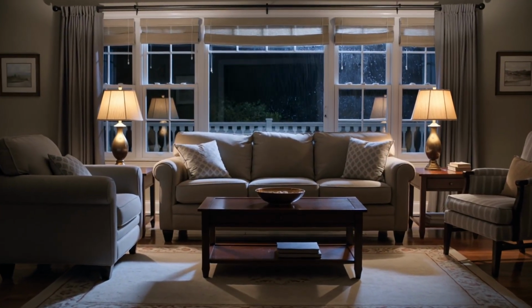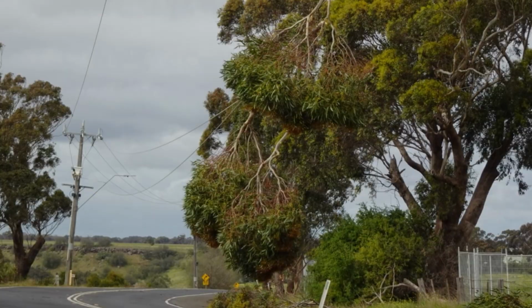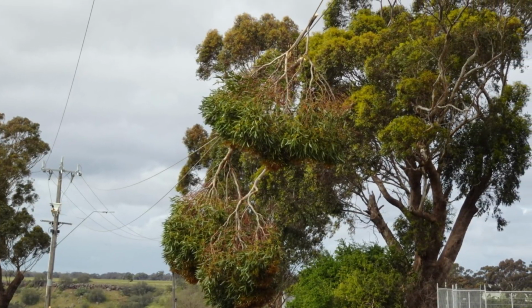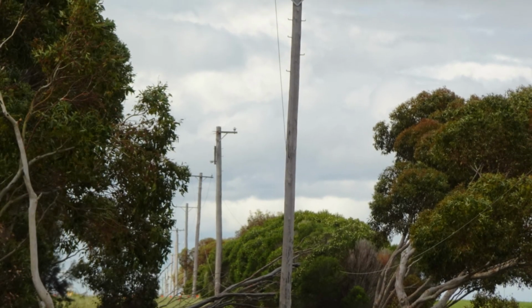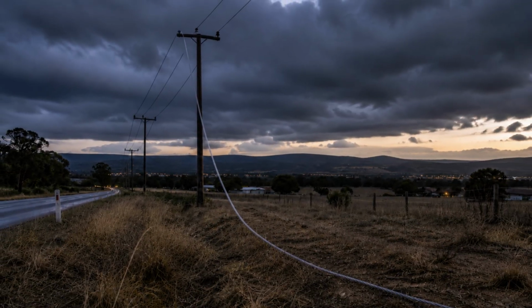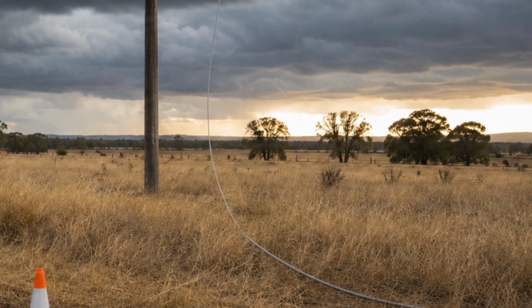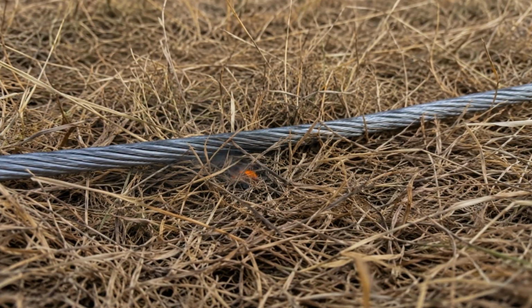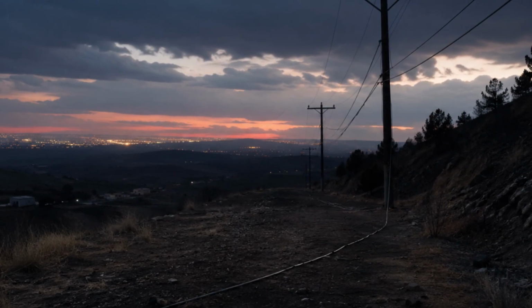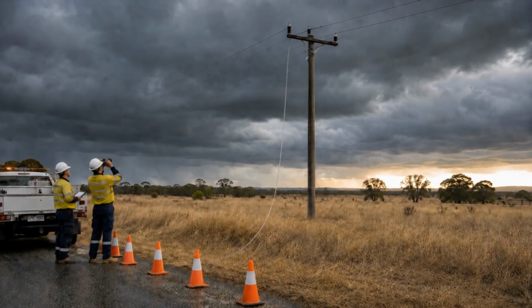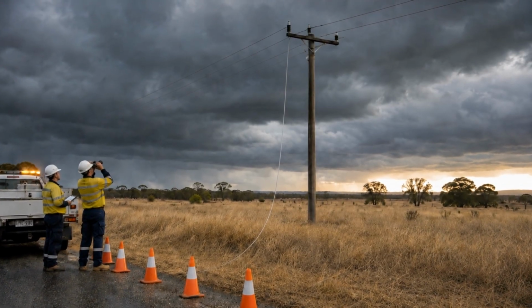But trying again is not always safe. In places with high bushfire or wildfire danger, that automatic retry may be turned off. If a wire has fallen into dry grass, switching it back on could create another spark and start a fire. So the line stays off until it has been checked. A longer outage can be the safer outcome.